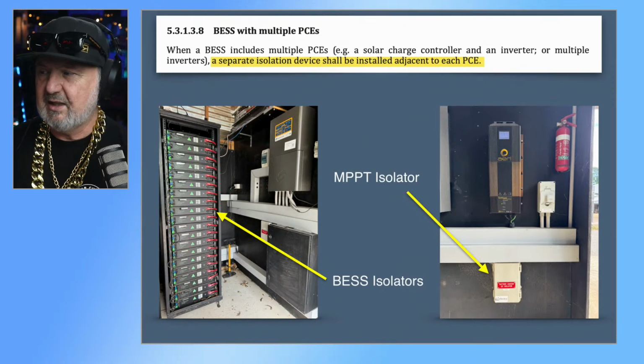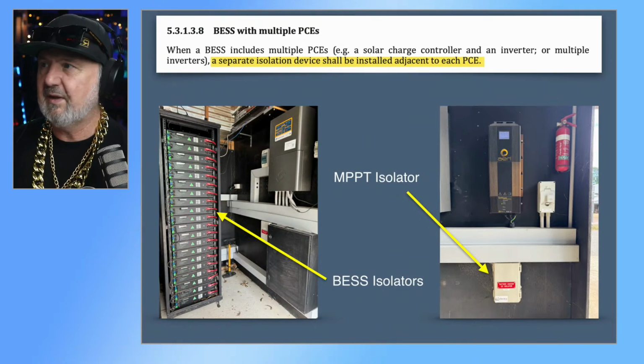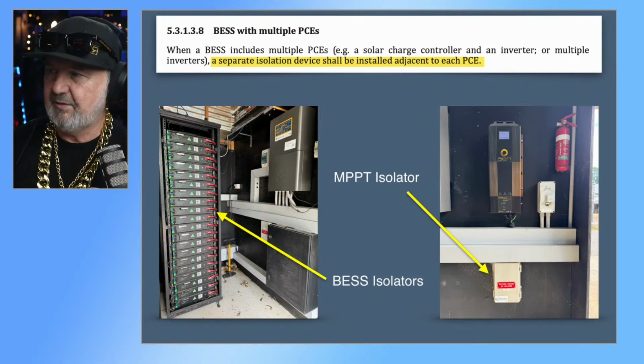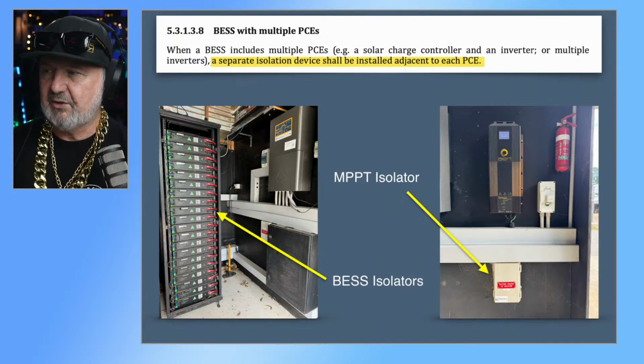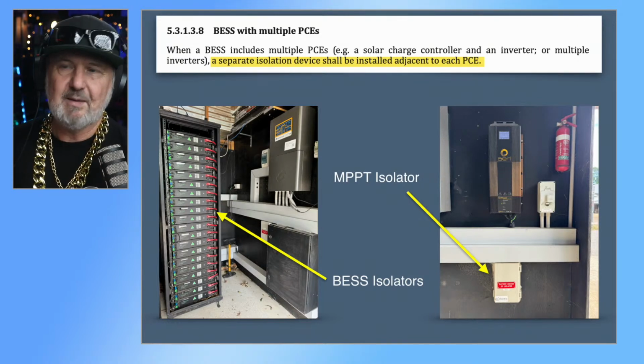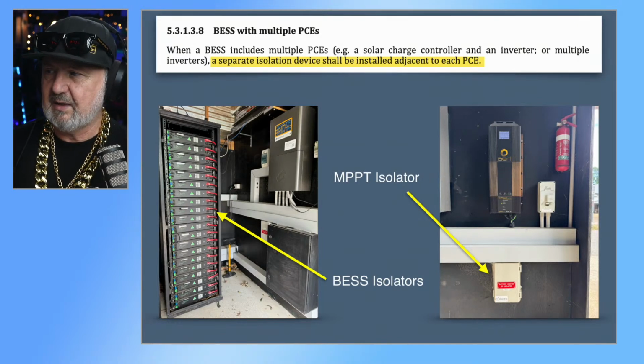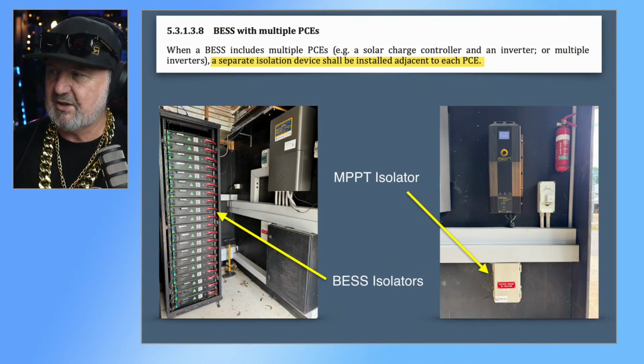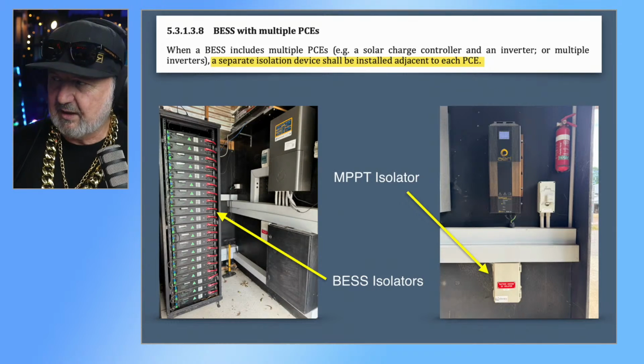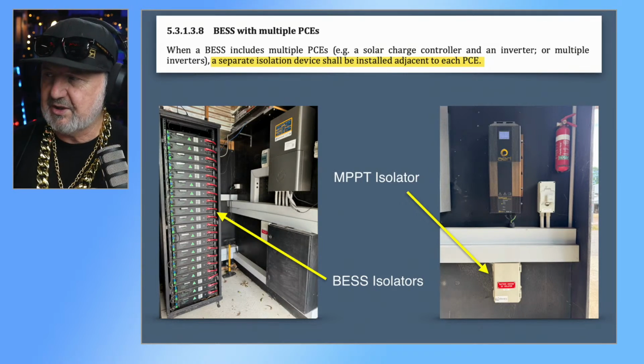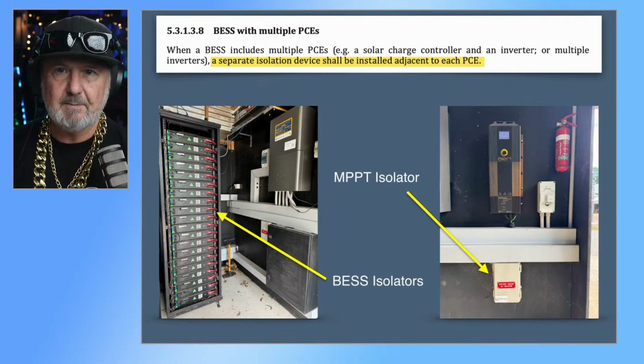Now let's look at the location of isolation with a BESS with multiple PCE. So when a BESS includes multiple PCE, power conversion equipment, such as a solar charge controller and an inverter, or multiple inverters, a separate isolation device shall be installed adjacent to each PCE.